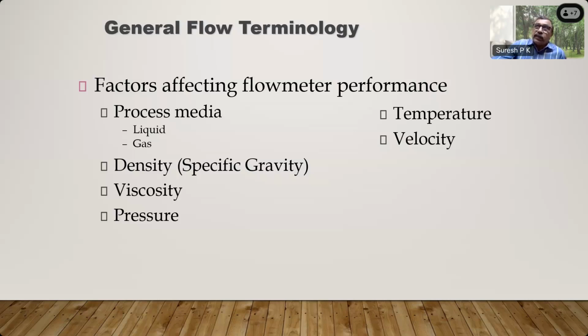You can make a proper flow measurement if you select the flow meter properly, install it properly, maintain it properly, calibrate it properly, and specify the conditions under which it is operated properly. The process media has to be given, and the density has to be given. You cannot use a gas flow meter in a liquid application, and similarly you cannot use a liquid flow meter for measuring gas. So these things have to be specified properly.